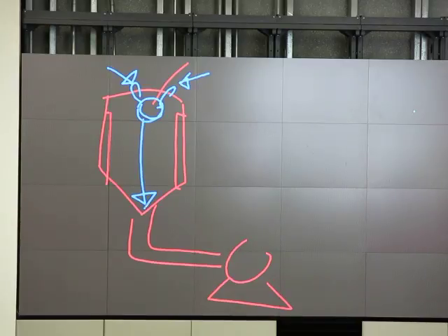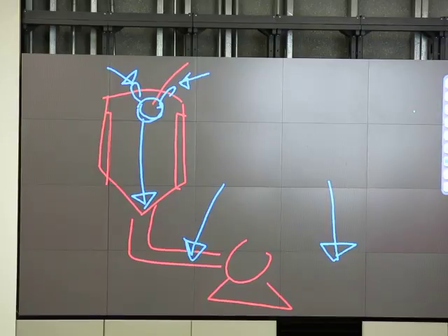What do you think happened? I don't think I have a suction relief valve or anything. I have a discharge relief valve, but I don't have a suction relief valve. So the pump cries or creates a very sharp noise. It's about to break. So we press the emergency shutdown.